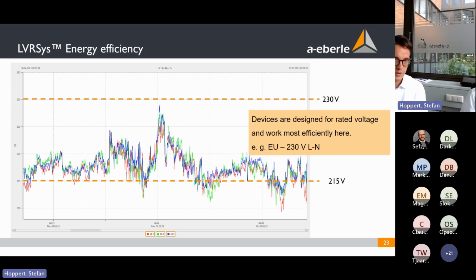Here you can see the voltage. The upper line shows the 230 volts, which is the nominal voltage here in the EU. And the lower line shows the average voltage, in this case, where it was 215 volts. I think it happens in a lot of grids that at the end of the line you get a reduced voltage, especially if you have just big loads connected, which will drop the voltage. The devices are designed for, and are working most efficiently with, 230 volts.